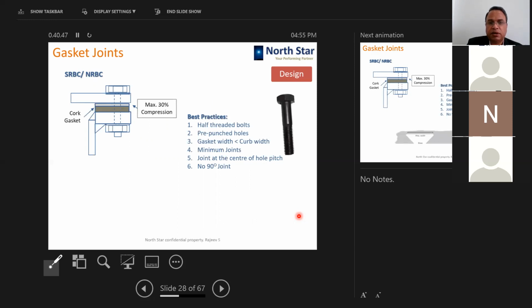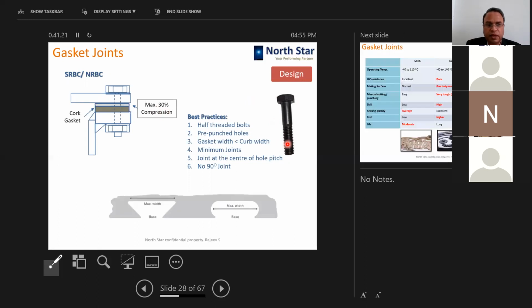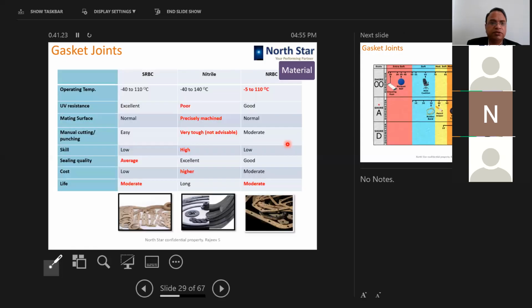Best practice: a half threaded bolt is a very good approach in preventing gasket leaks, because this half threaded portion sits in this and the gasket actually holds that bolt. But if you have a fully threaded bolt, then because of these threads, the oil can seep through it. I am not saying it will seep, but the possibility of leak with a full threaded bolt will be higher compared to half threaded bolts. This is the way the dovetail joint should be made.